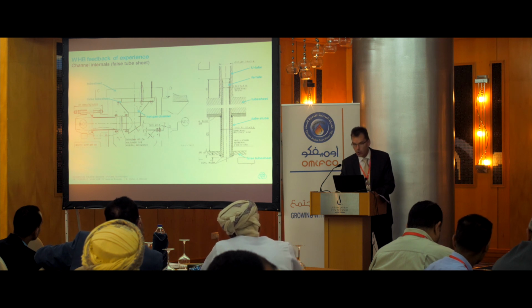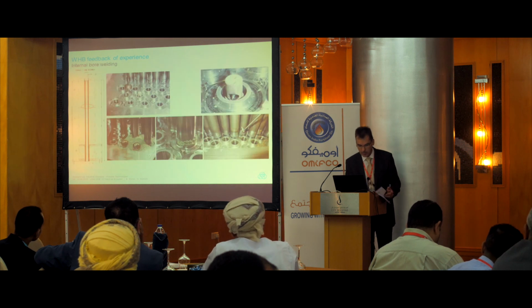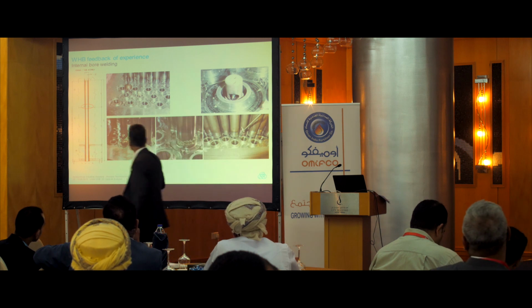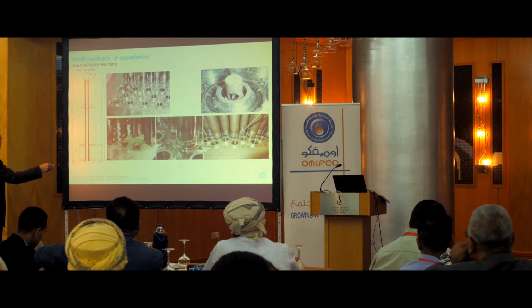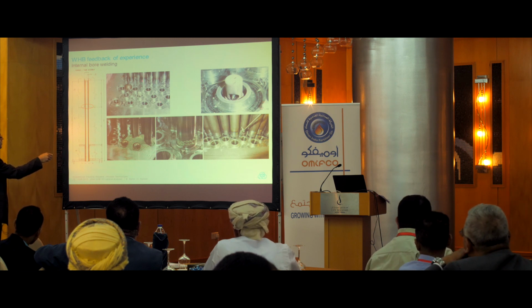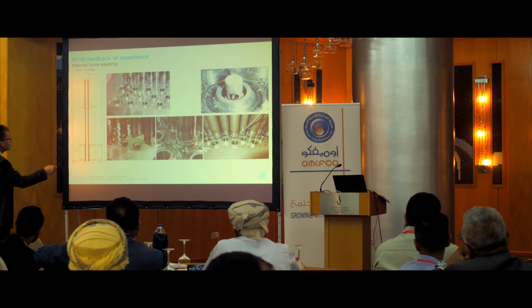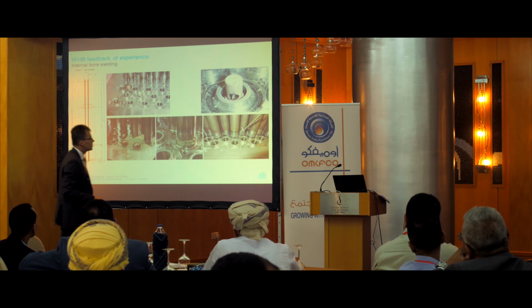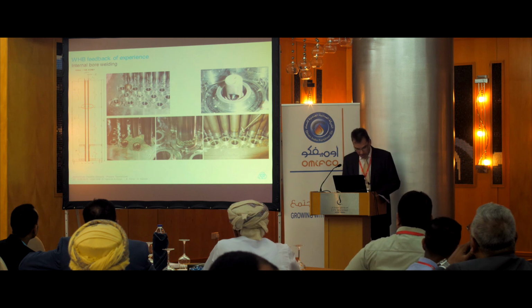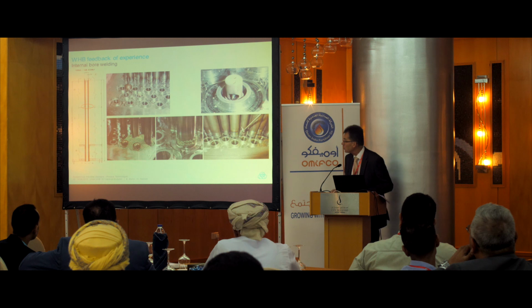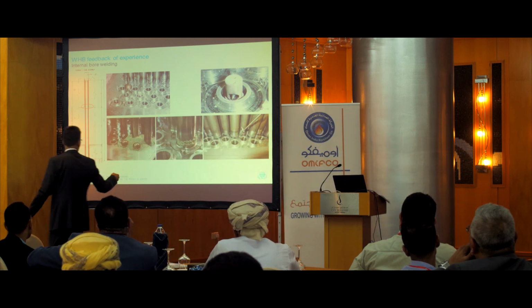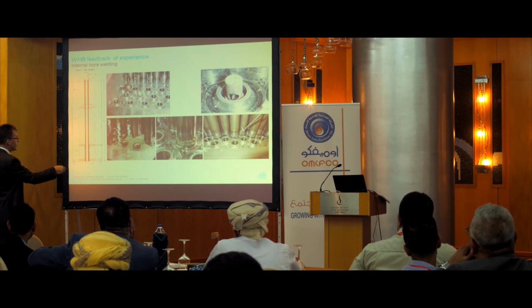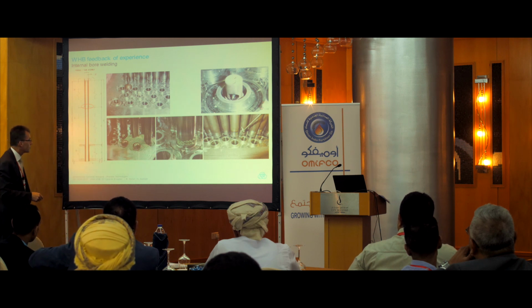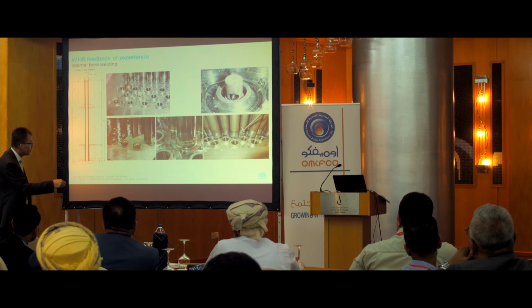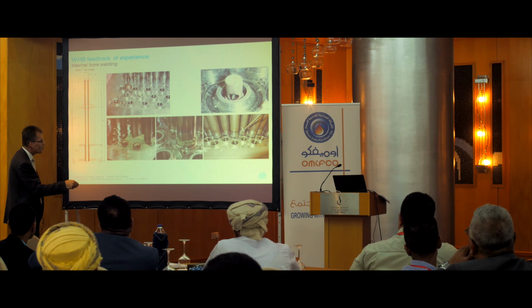Let's have also a look at what internal bore welding is. I can present you some pictures which give you a better idea than words maybe. On the left side, you see the tube sheet itself, and on the top of the tube sheet they have milled so-called hubs. On these hubs, the tube will be placed, and inside the tube will come up from underneath. Here is a better detail. It's a tungsten arc welding torch, and the welding will be done by shielding inside the tube with argon, and outside we have the so-called welding flux, the welding powder located outside. The balls here are just put in by hand, so that the weld flux will not fall into the tubes. Later on, after welding, you have this kind of look. Then you remove, of course, the rest of the flux, and then you have a good access normally, tube by tube, to check it, not only visually. Yeah? You can also do RT tests here.